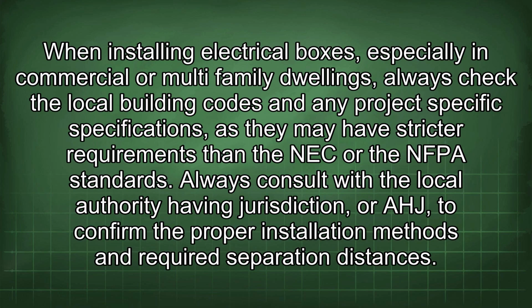When installing electrical boxes, especially in commercial or multi-family dwellings, always check the local building codes and any project-specific specifications, as they may have stricter requirements than the NEC or the NFPA standard. Always consult with the local authority having jurisdiction, or AHJ, to confirm the proper installation methods and required separation distances.